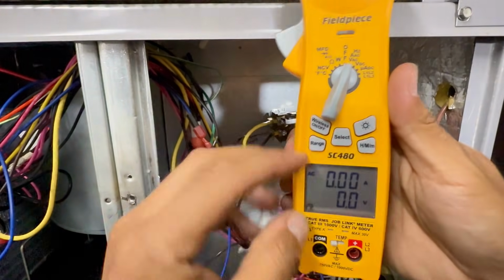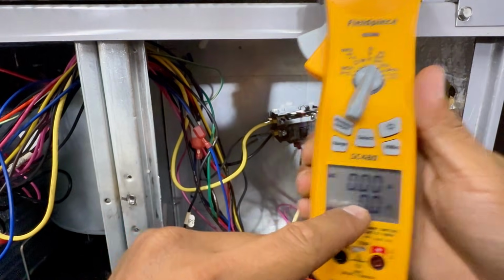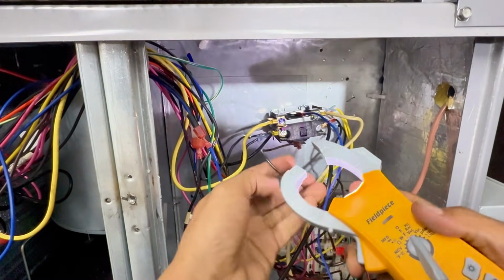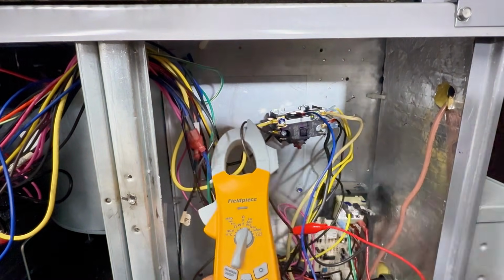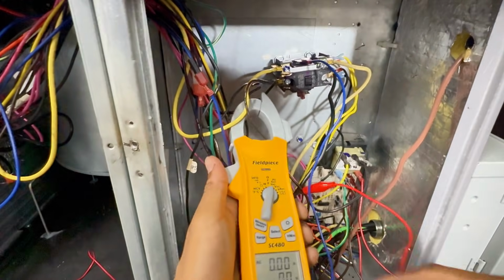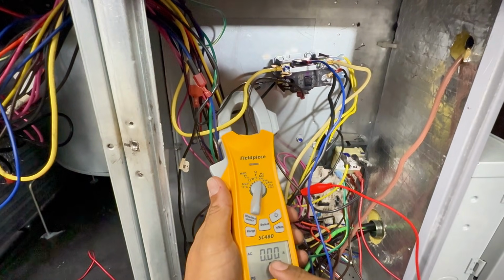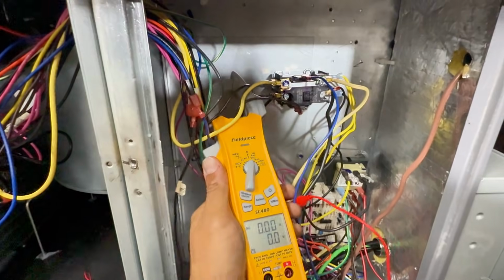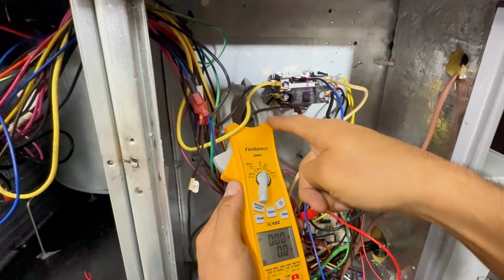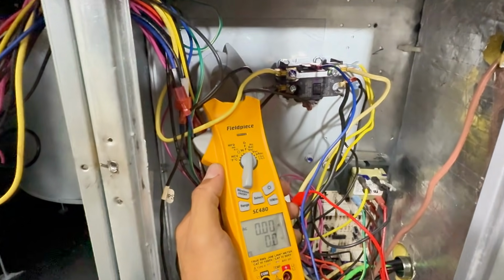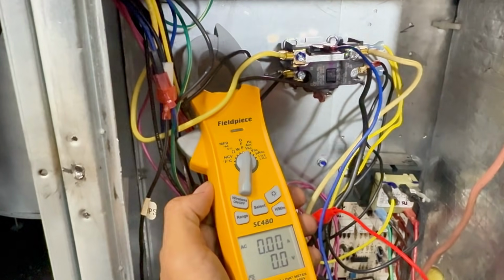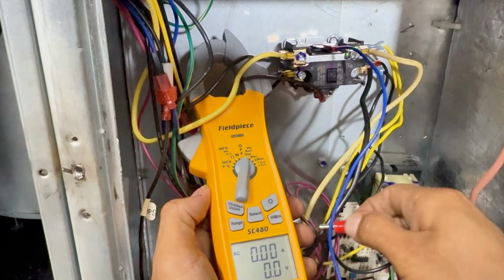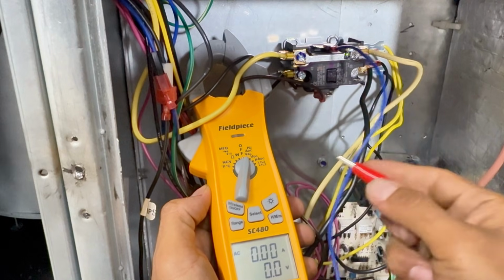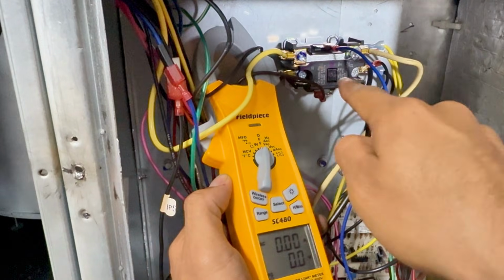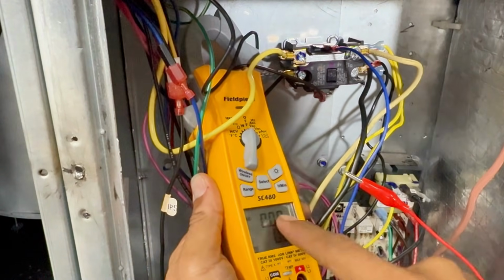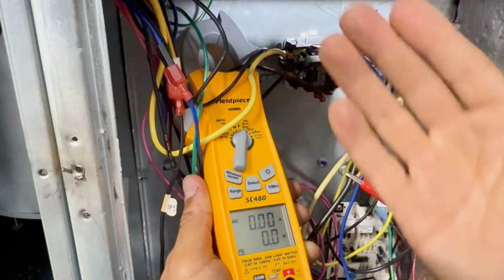If I go ahead and get my meter, put it on AAC, amp draw, I'm gonna go ahead and put it around the common, okay? And let's just get situated so you can see 0, okay? So this is what I want you to pay attention to though, right? My wire is gonna stay there. Once I energize that contactor coil, I actually have 24 volts right here present with me. Once I energize that and that gets pushed in, you're gonna see that change, because now there's current going back and forth.